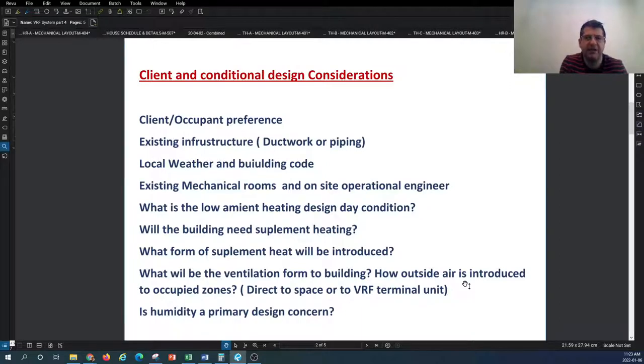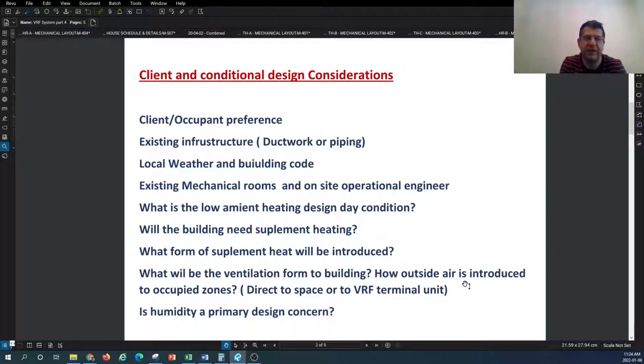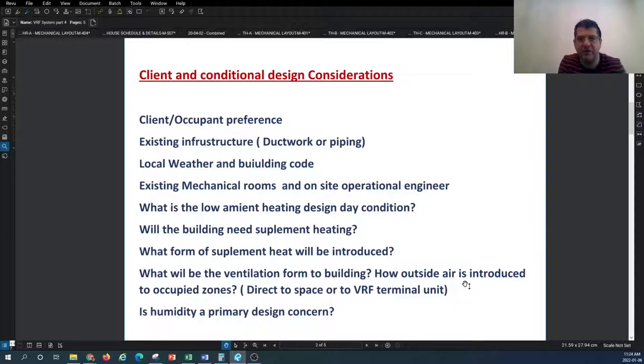The lowest ambient heating design condition is a concern because you need to understand if supplemental heating is needed. When the VRF runs in heat pump mode, the outdoor condensing unit has a limit on the minimum temperature range. If your geographic area experiences temperatures below minus four degrees Fahrenheit or lower, your heat pump may not operate efficiently enough to cover the entire heating load, and you need to consider alternative supplemental heating such as perimeter radiators or other systems that can boost the heating demand.